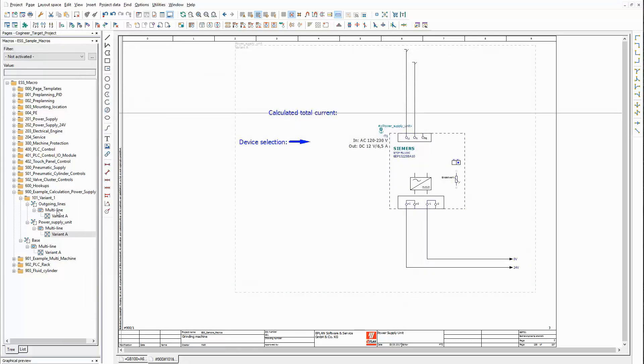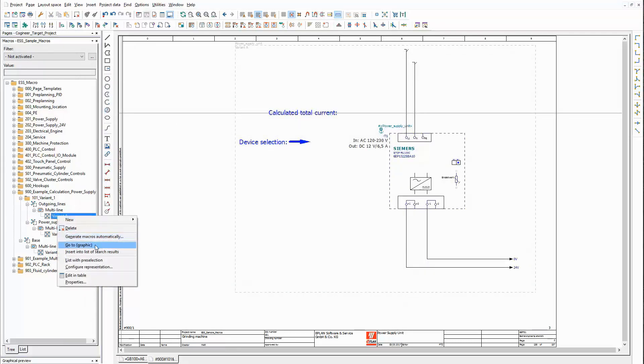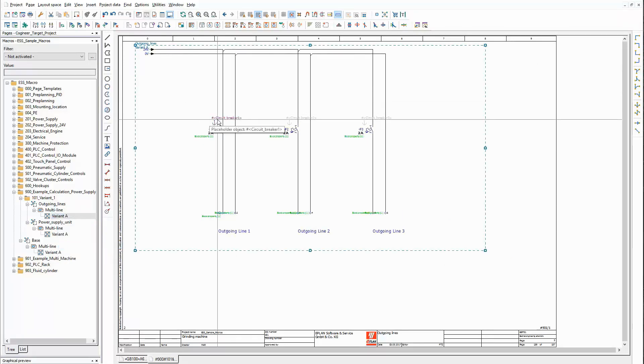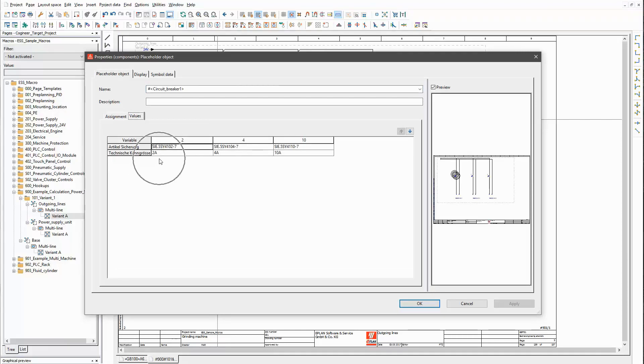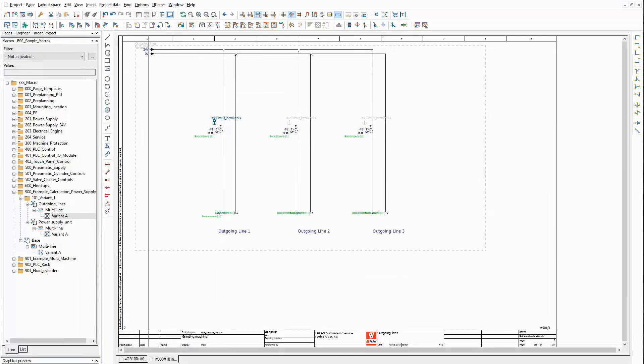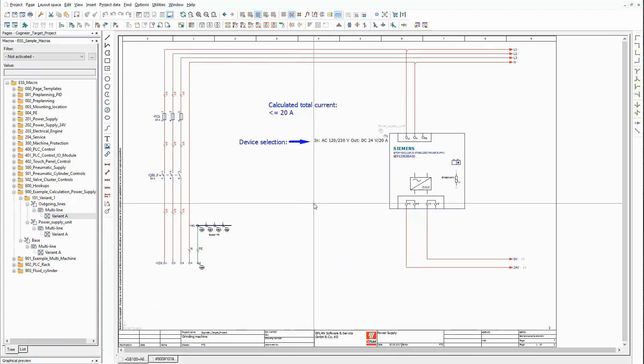The next macro contains the schematic for the outgoing lines. This time there are three placeholder objects. Again, you have to use this syntax to make it available in ePlan Cogineer. Each of them contains three value sets. This time the variables are connected to the properties part number and technical characteristics. Therefore the values that are set for these variables are used for these properties. This is how you can set up an intelligent parts selection depending on simple calculations.